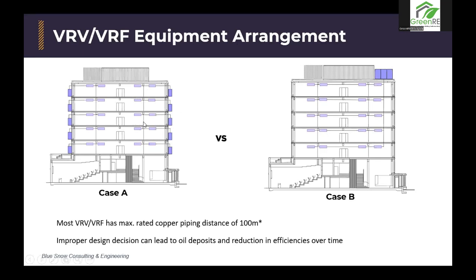So case A, in a rectangular building, that's a bit oblong shape. One person decides to put it on each level. The other person has done it on the top level. That means they want to keep it neat because they want a beautiful facade. They put all the outdoor units on the top, and they just pull the copper pipes all the way down to the furthest end as well. Both are actually okay, but there's a caveat to this. The VRF and VRV system, most suppliers will rate it at a 100-meter max distance for the copper piping. Again, sounds like a lot. There shouldn't be an issue, especially for a 3 to 4 storey building. But you will need to actually size those copper pipes if you're going for case B. Even case A, you need to properly size them.